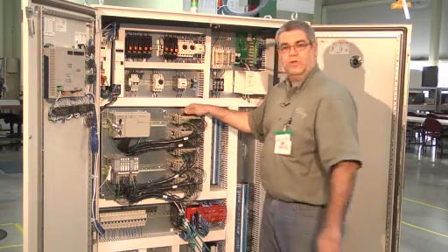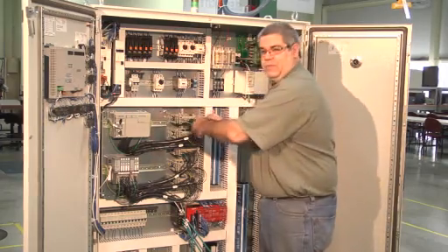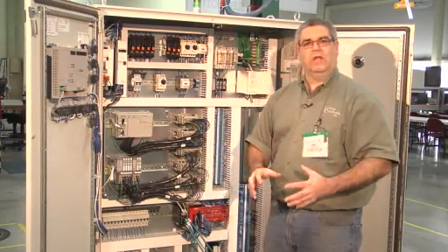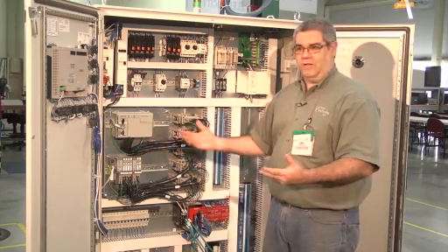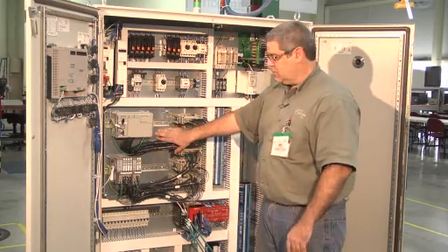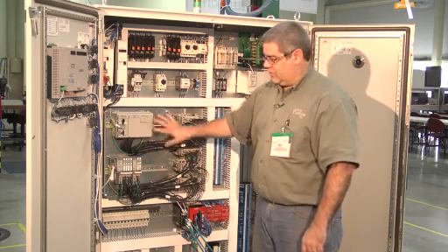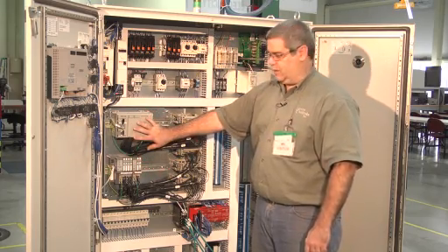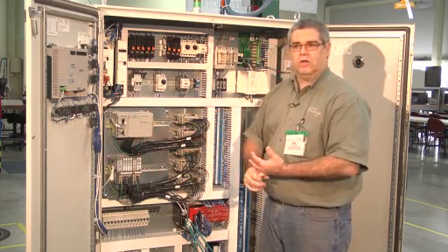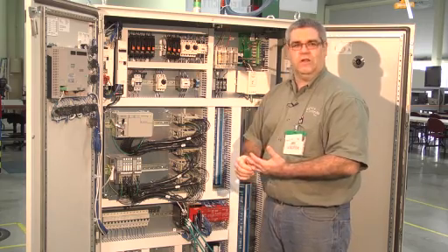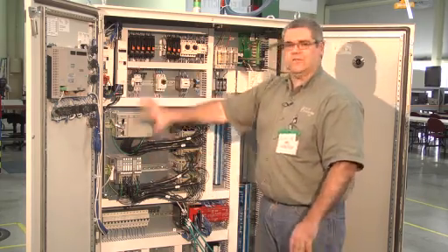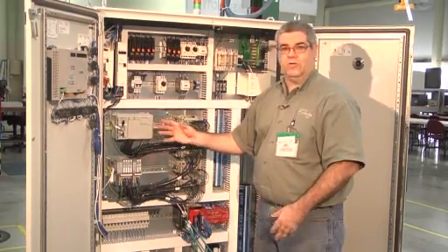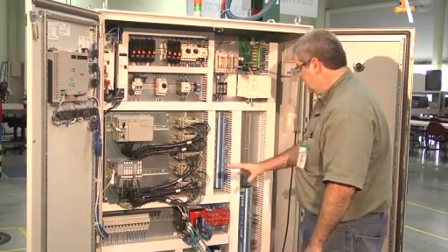You can do it with the built-in wiring, or you can just unsnap these and remove the plate and potentially change to another brand, Siemens, Modicon, Telemecanique, whatever, to operate it. The I/O was picked here with analog. So there's analog 4 to 20, there's 0 to 10 volts, discrete ins and outs, so that it's a standard one. Almost every brand has all those specific type of boards.